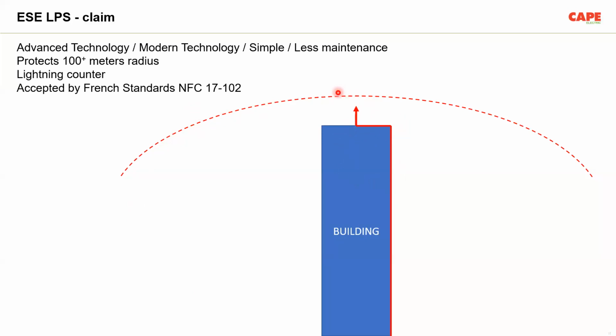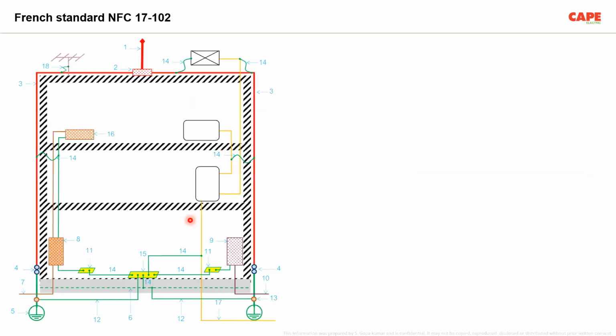And the most interesting point is, if somebody says this installation is wrong, or ESE is a wrong method, then immediately the manufacturer says, no, it is accepted in the French standard, it is accepted in a lot of European standards, and French people are not fools. If the French can accept this system, why not India? This is the argument. Please understand how these installations are made in India. It has one rod, a simple 70 square millimeter wire running down the floors, and then there is one earth pit. And then they claim this is as per the French code.